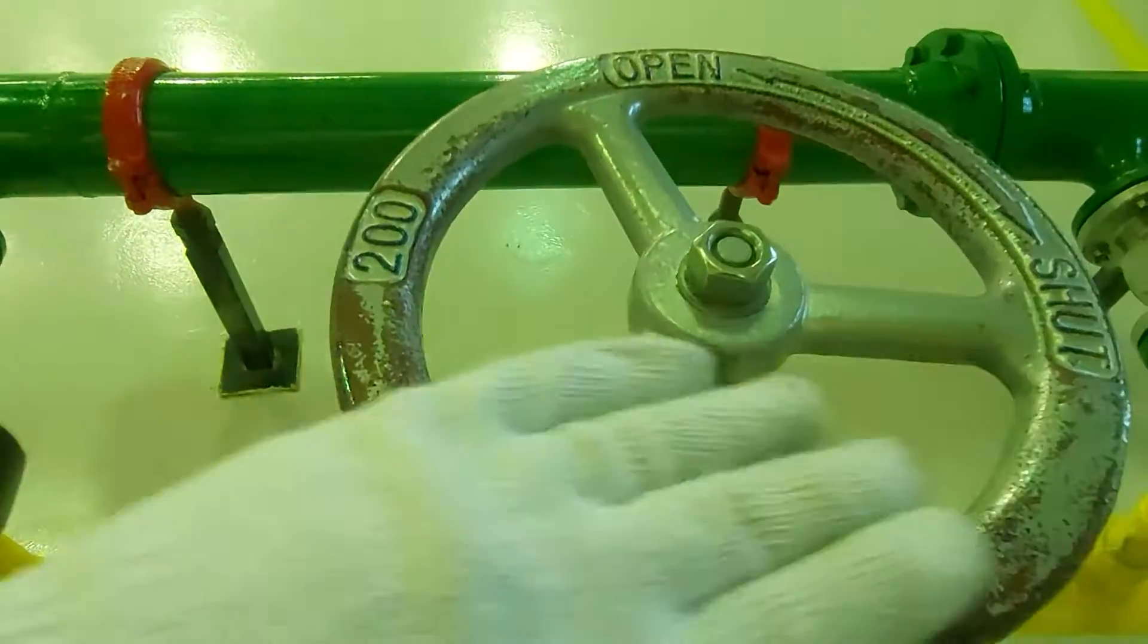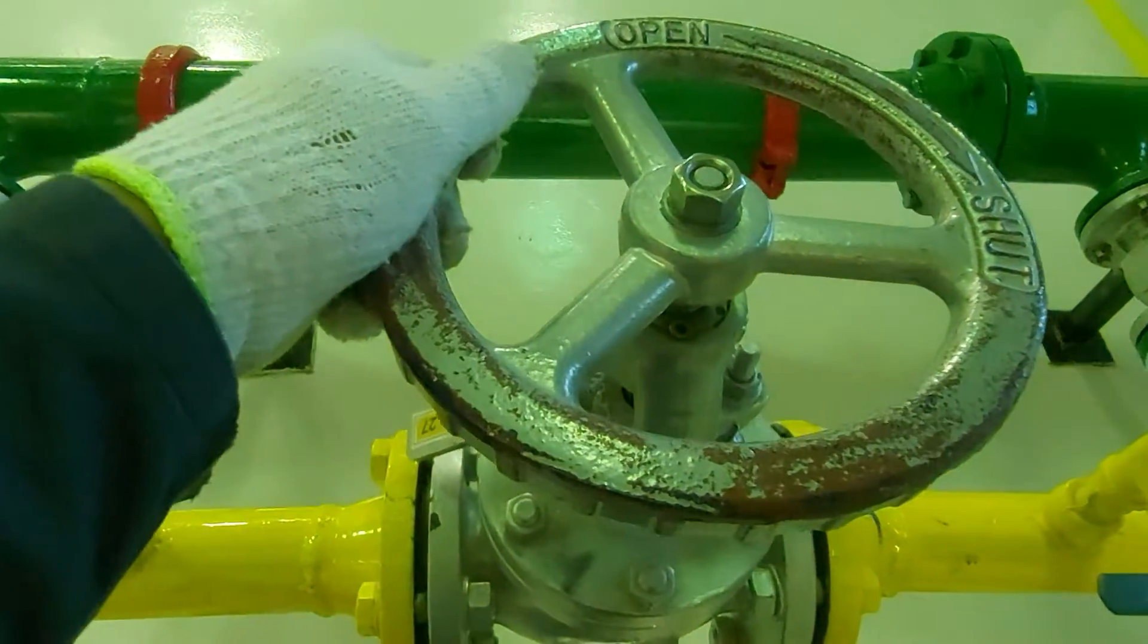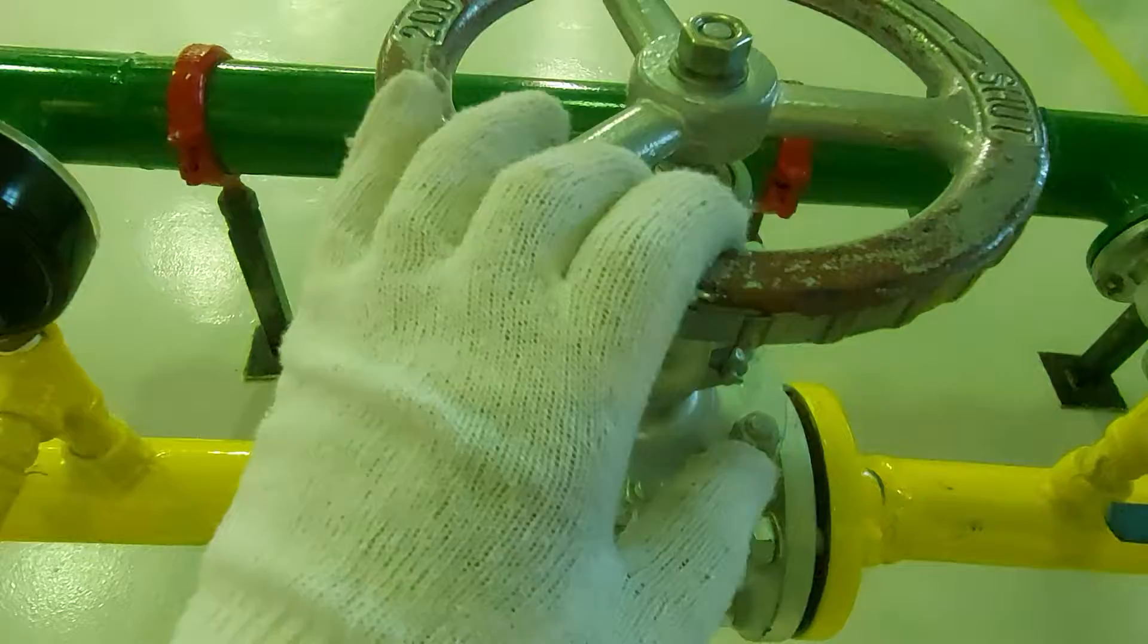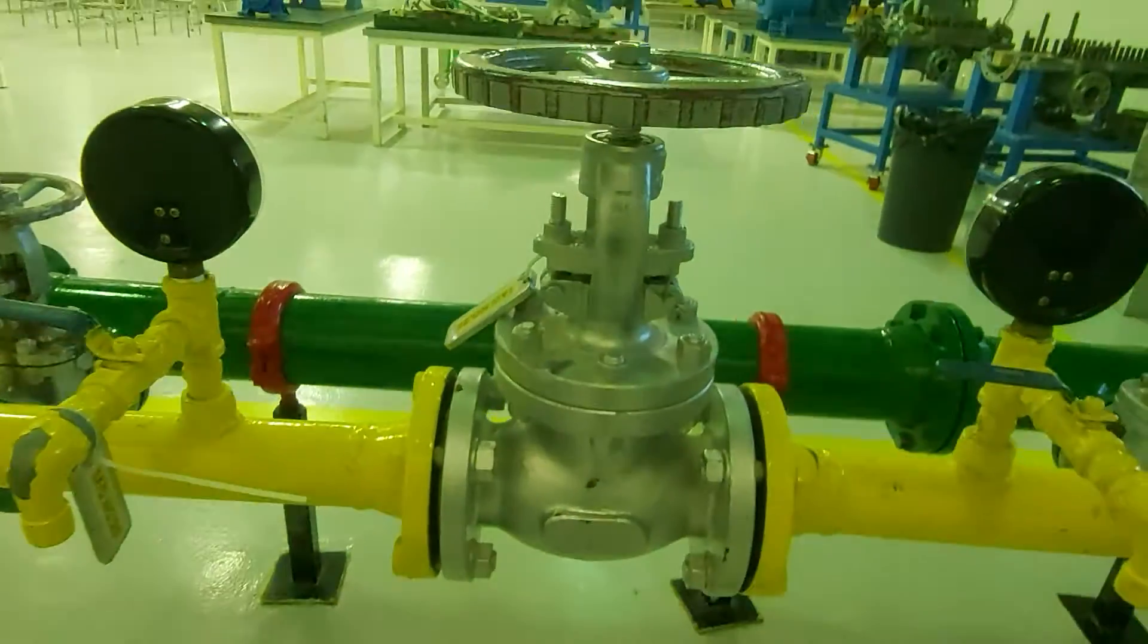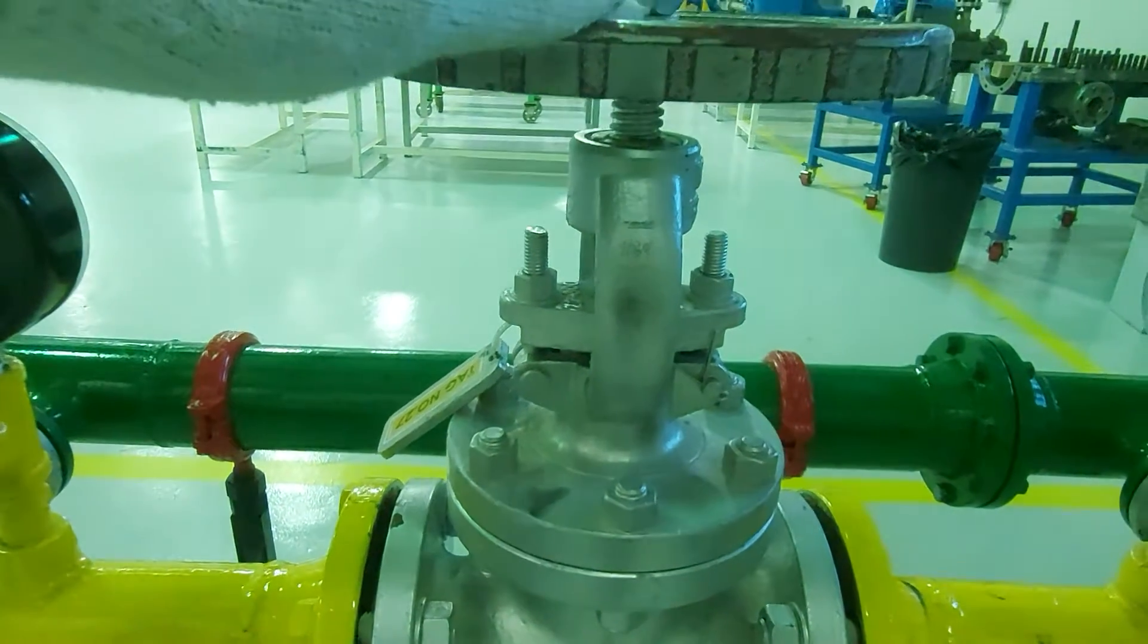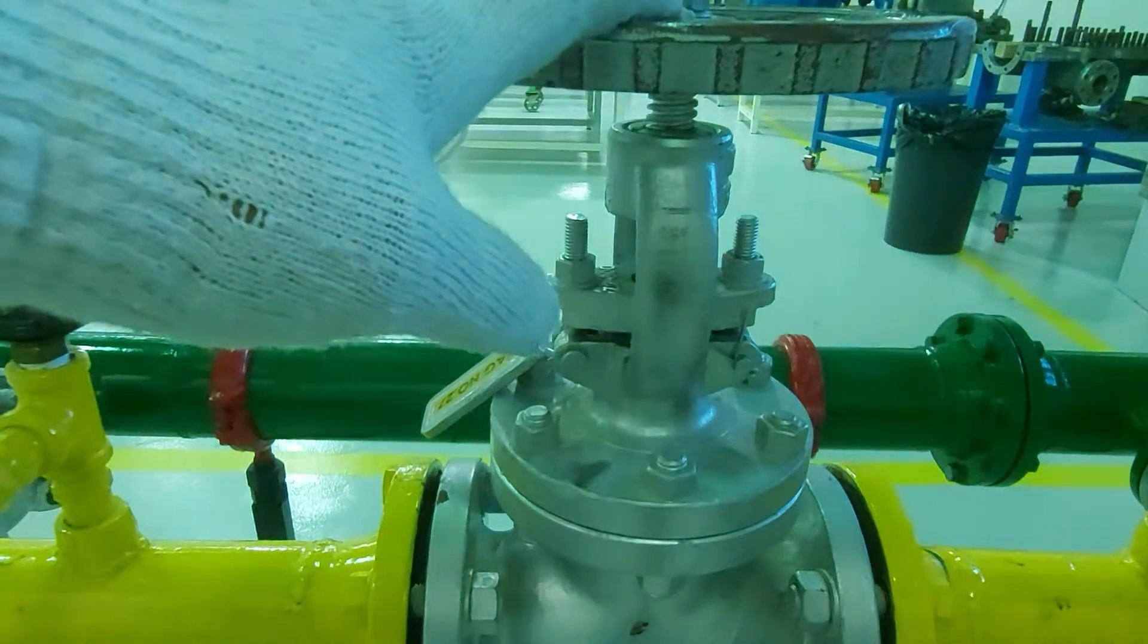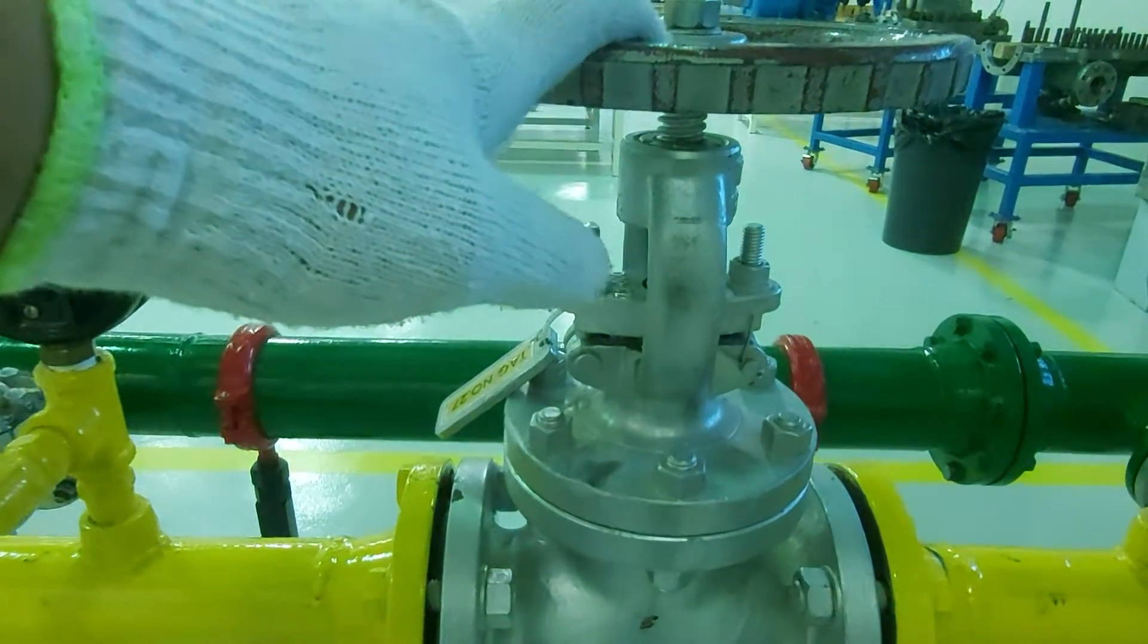Now, how to know from far away that it is open or closed? You have to see the stem. If you see the stem, you will know that it is open or closed. Now we don't see the stem, so it is closed. Let me open it for you and you will see how the stem will be visible.